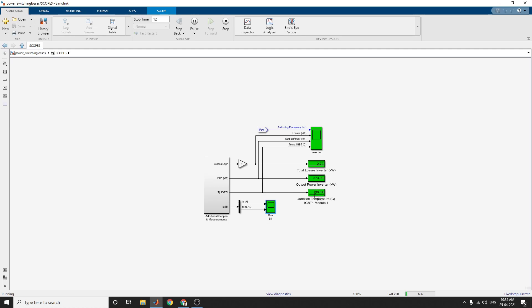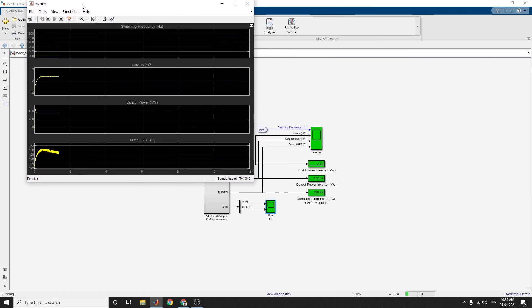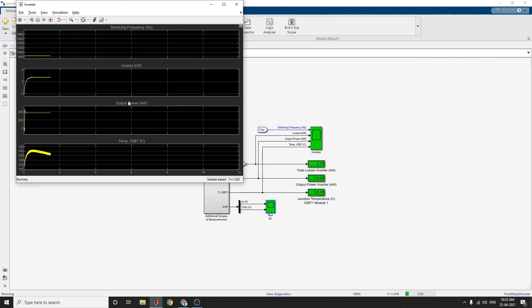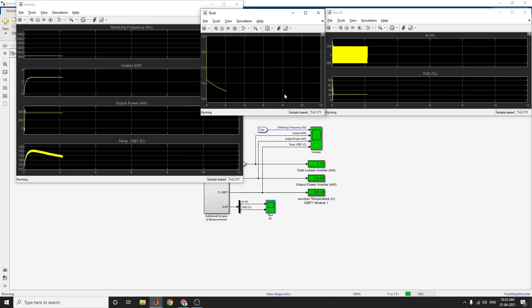The maximum junction temperature in the IGBT model is 125 degrees. For example, the inverter output shows switching frequency, losses in kilowatts, output power in kilowatts, and junction temperature in the IGBT model. The bus B1 output and the maximum junction temperature of 125 degrees can be observed here.